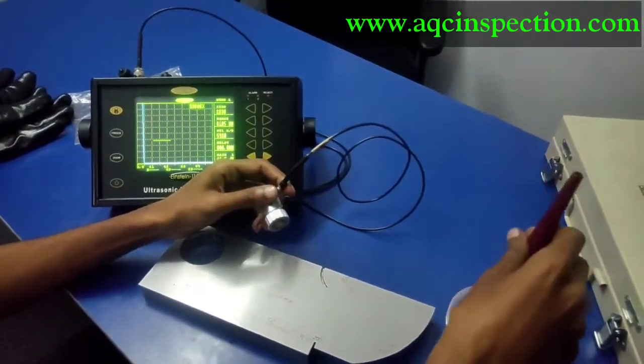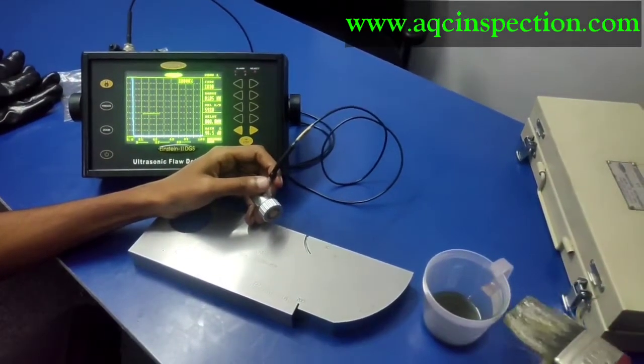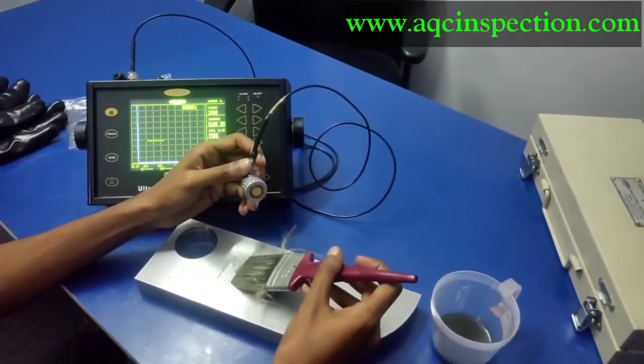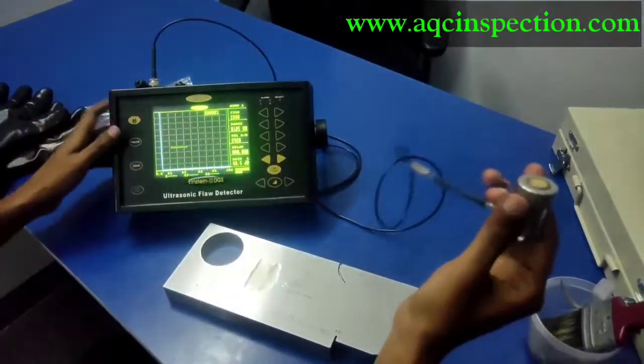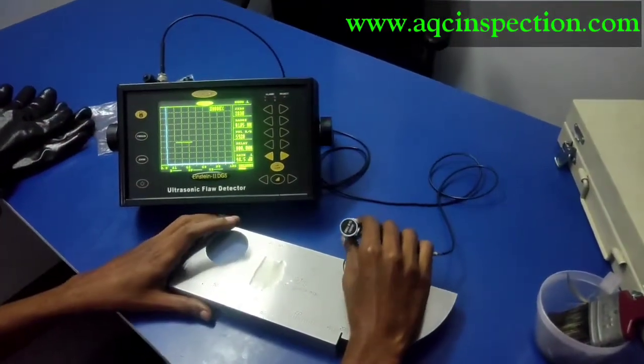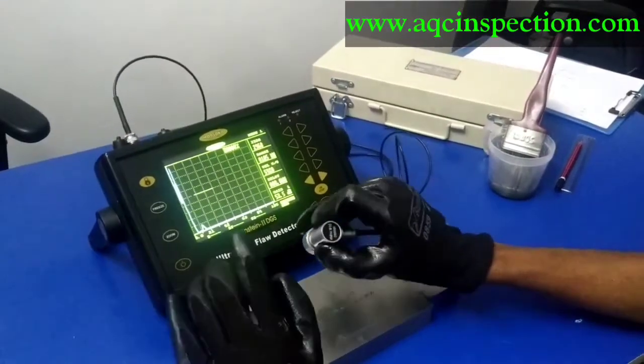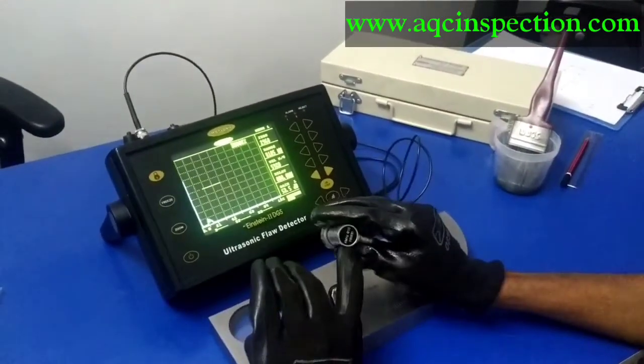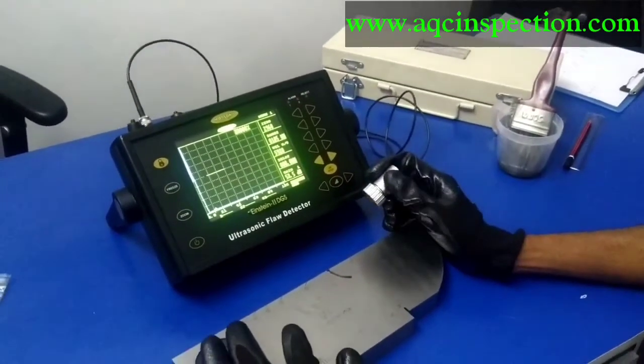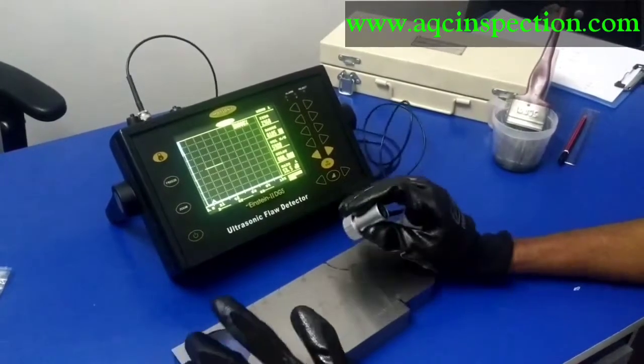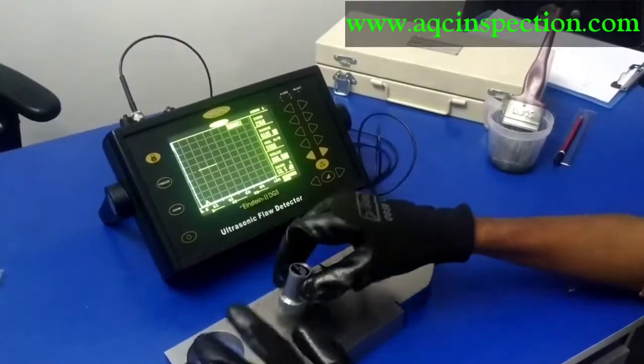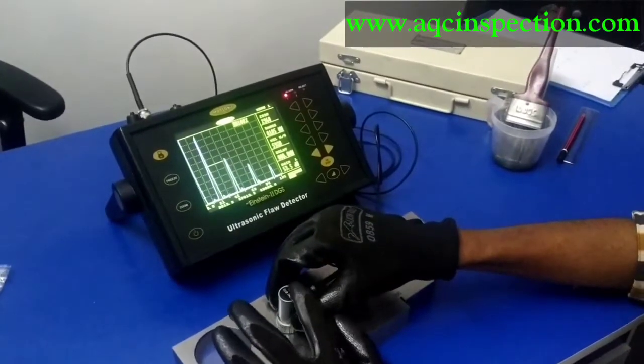First, we have to put a couplant. I am going to use an oil only. Just a 2T oil, normal motor oil. Now we are going to calibrate the 10 mm diameter crystal, 4 MHz frequency transducer using the V1 block right here. I have already applied the couplant. I have put oil, 2T oil, motor oil. So first what I am going to do is place the probe on the V1 block.